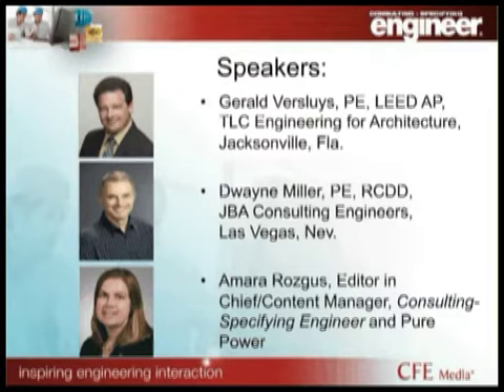And now you can really leverage the generators not only for backup, but also for other means, combined heat and power for the building or for cooling, drive an absorption chiller with it, cogeneration. There's so many different ways to go with that. So I think it would be easier for a large-scale resort to be able to get that on because they've already got this infrastructure in place to basically island the property, and the more efficient they can make that system, the better.